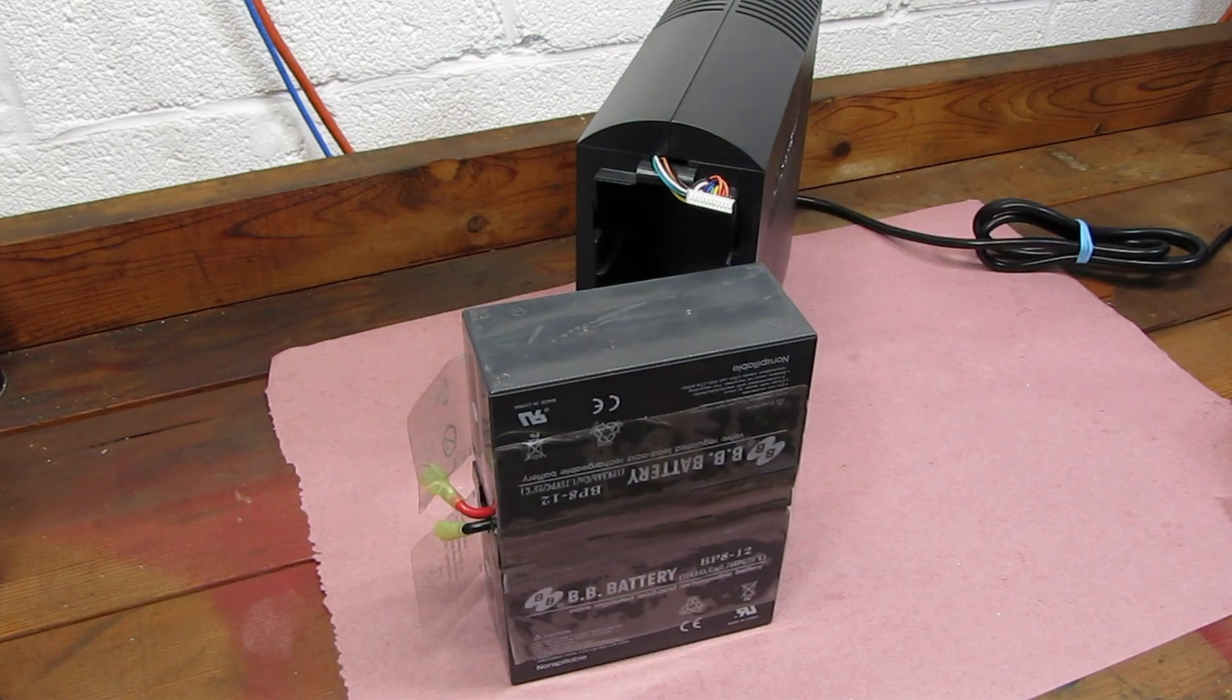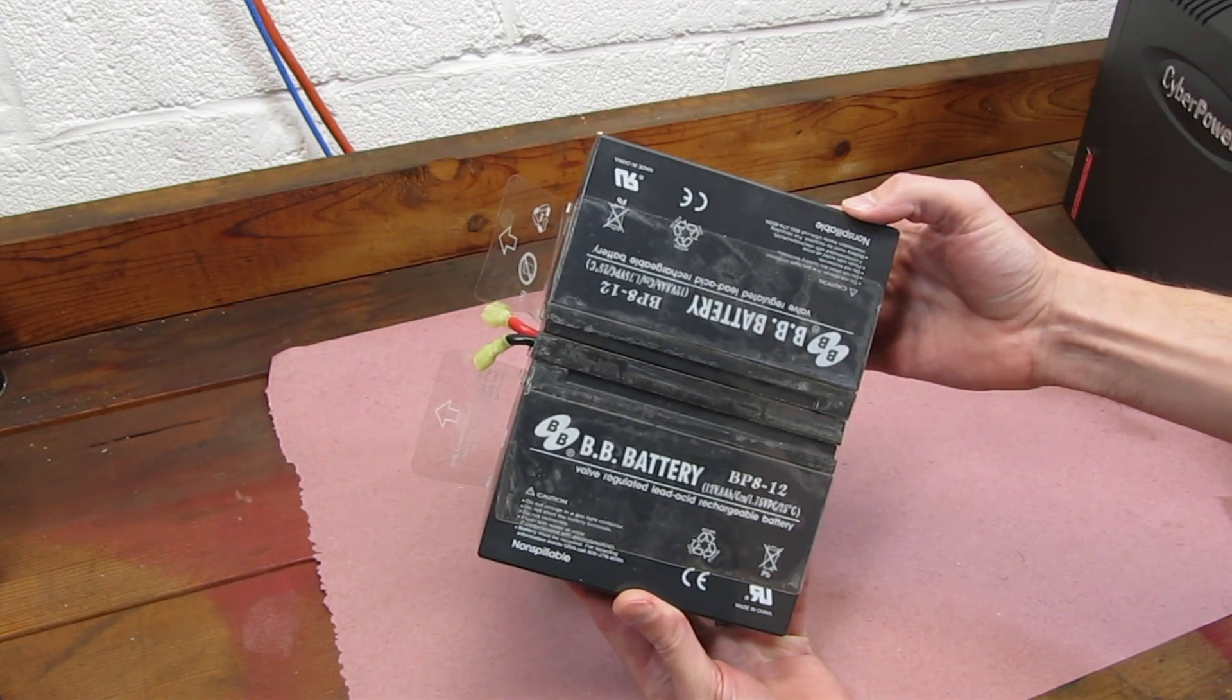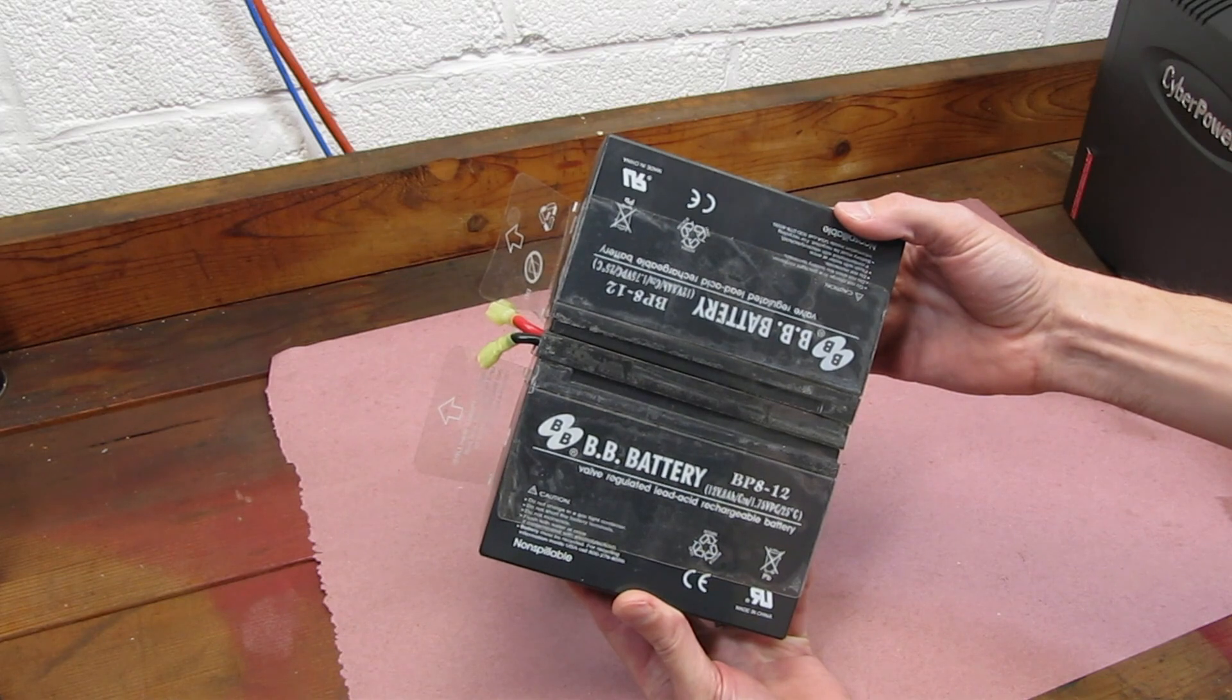Sometimes the batteries can swell and may be difficult to remove. Just keep working at it carefully. Generally, when the UPS fails, it's these batteries which have failed.